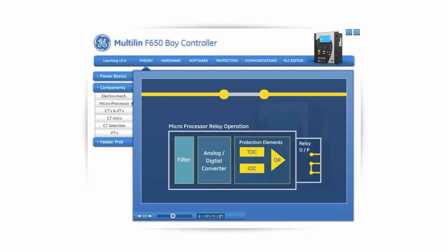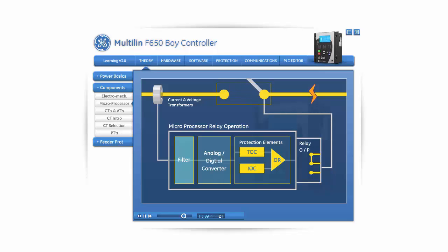Let's take a closer look at the operation of a modern microprocessor-based relay. Through the use of current and voltage transformers, the relay receives information about the power system. These quantities are converted into symmetrical components and passed on to the active protective elements within the relay. The protective element or elements within the relay initiate the appropriate action based on these quantities and the configuration settings within the relay. These elements may work independently or through the use of logic gates.